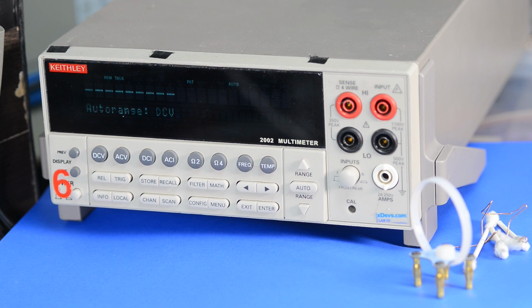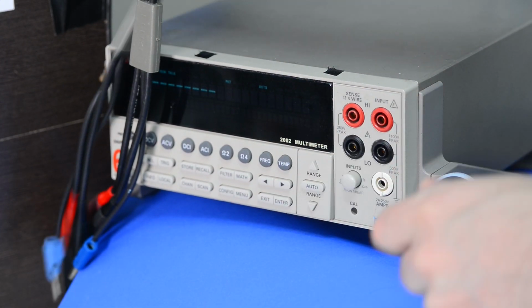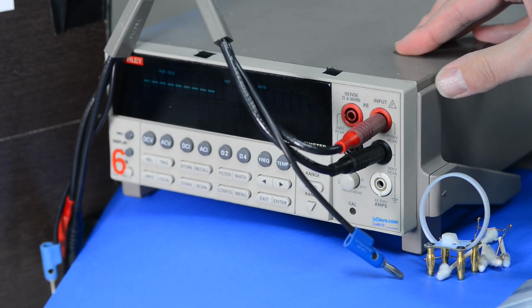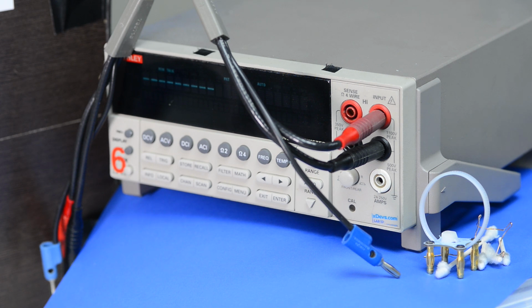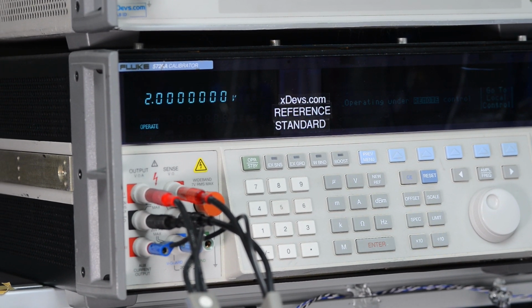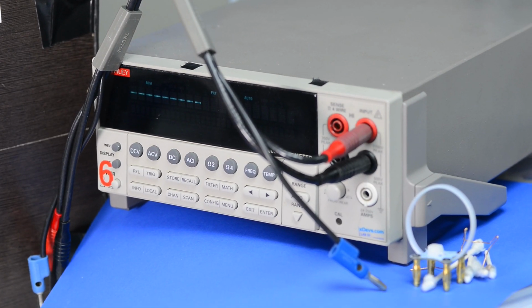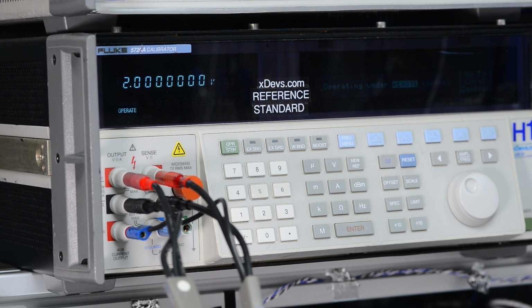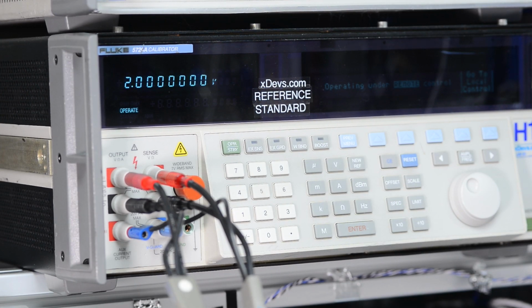So next we need to connect 4-wire terminal short and perform the calibration for 0. And after this, we will need to connect 2-wire terminals from calibrator to start with DC voltage adjustment. So the first point is 2 volts, followed by 20 volts, and so on. To save time, this video is actually faster than real time. The whole procedure in real life takes about 15 minutes or so. And when instrument is calibrated using remote control from GPIB, it does not show display readings. So you will have to navigate through different calibration steps using the procedure coded in a host computer.